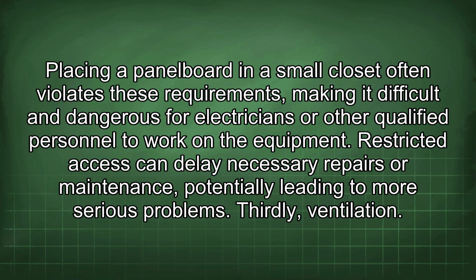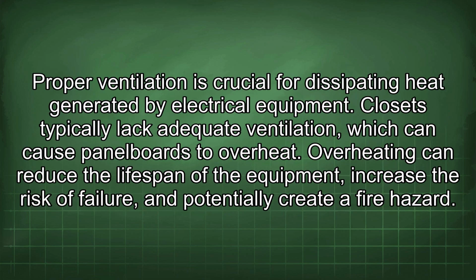Thirdly, ventilation. Proper ventilation is crucial for dissipating heat generated by electrical equipment. Closets typically lack adequate ventilation, which can cause panel boards to overheat. Overheating can reduce the lifespan of the equipment, increase the risk of failure, and potentially create a fire hazard.